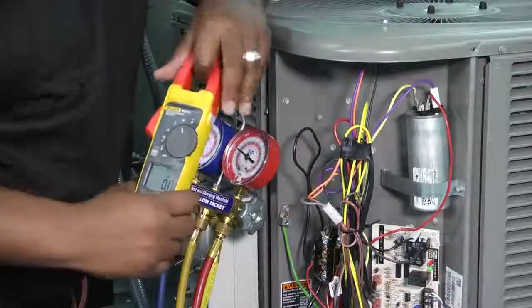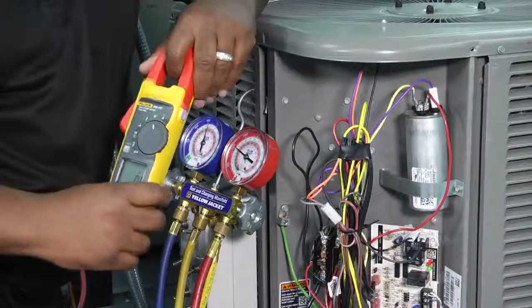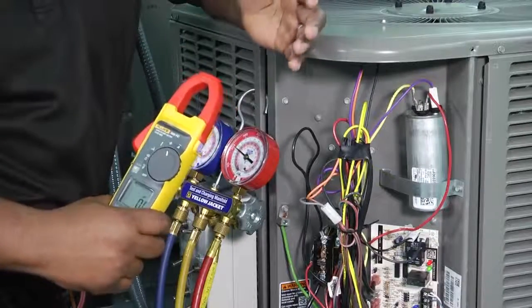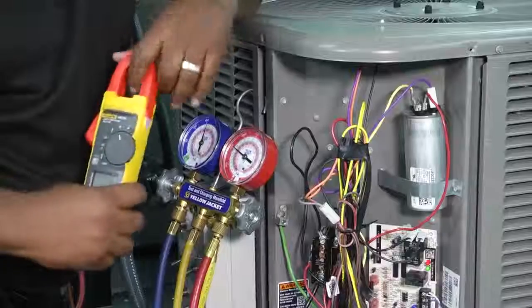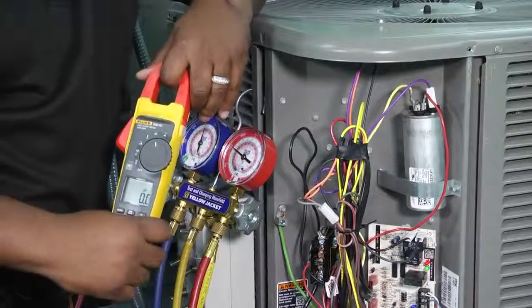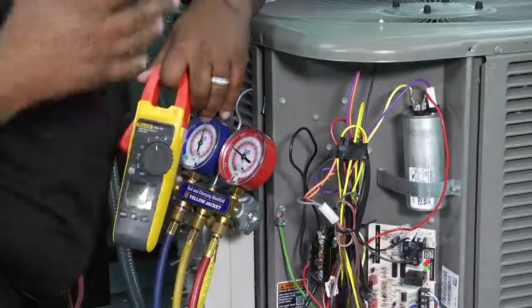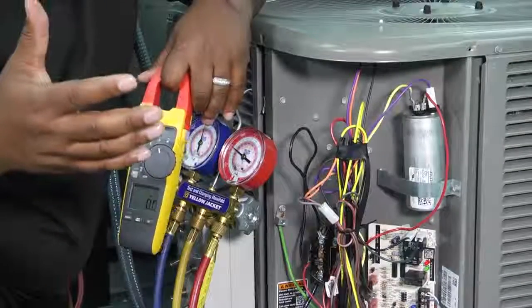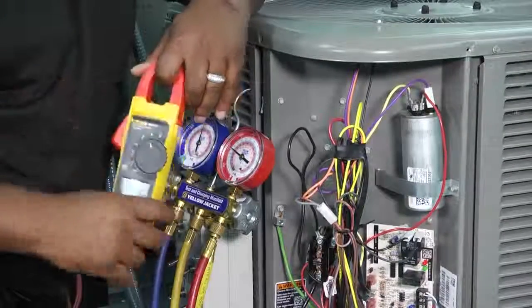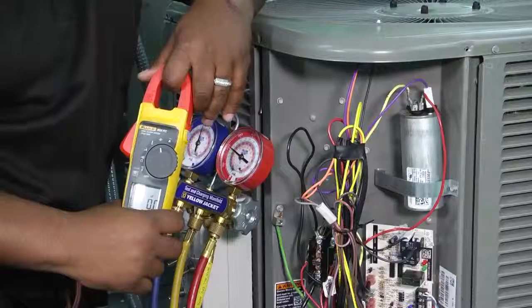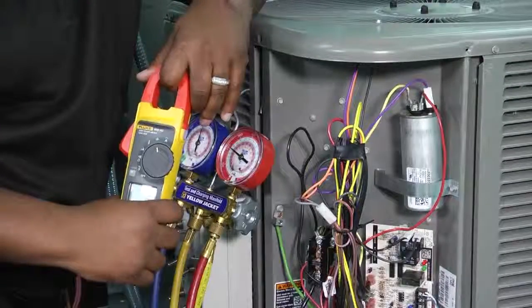So that's checking your capacitor. There's another capacitor that you also need to check, because our indoor blower motor, which is located inside of the house, also has a capacitor. If it doesn't, and it's a variable speed or ECM motor, then we may have to use one of those testers to test that. But don't forget to check our indoor unit as well.